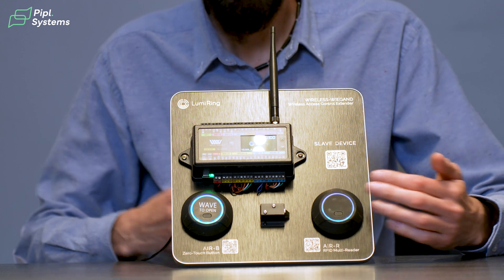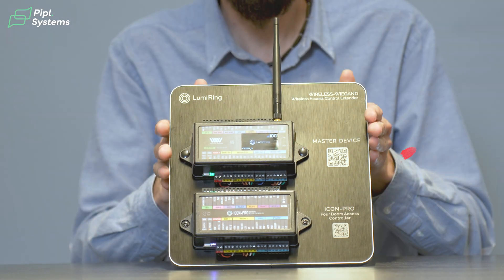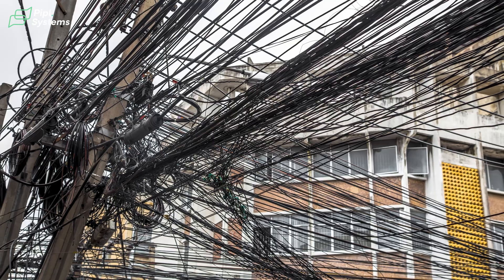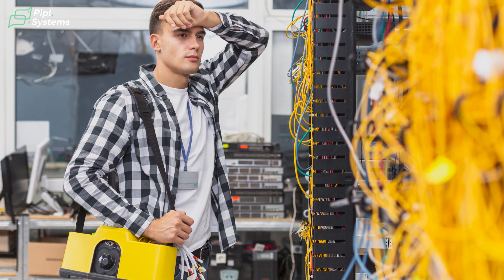The idea is that you have a remote end — this one — where you have the door, readers, lock, and request-to-exit buttons, and a head end where you have the controller and the brain of the system. These two things are normally at a big distance. You may have a gate somewhere remotely, you have garage doors, all of those things. And in between you have to put wiring, and that wiring consists of many strands — there is a Wiegand or OSDP interface, there is power, there is a lock, there is a door sensor, there are many things. And this wiring is sometimes quite difficult to install, and in some projects it's impossible.